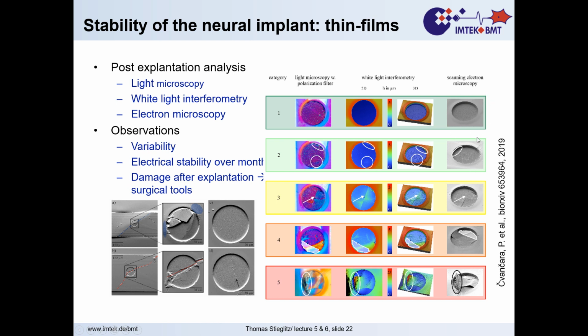We see really pristine electrodes and some crests that might come from material changes and intrinsic stress in the thin film. That is where we still want to dive deeper into material analysis to find out what this really is. And we are lucky that we have a brand new toy in our laboratories with material analysis options, and we are currently looking at that. TOF-SIMS is one of them: time-of-flight secondary ion mass spectroscopy. You can grind layer by layer from those devices, and the residues fly into a mass spectrometer, and then you get an idea if there's, for example, more sodium or more chlorine in your platinum or iridium oxide than there should be. And this gives you a hint about the material composition and if materials change in the present or in the body.